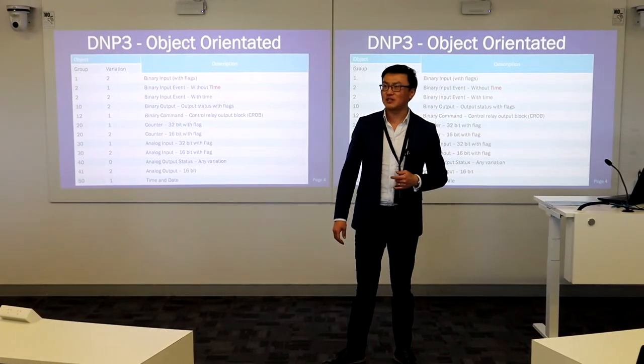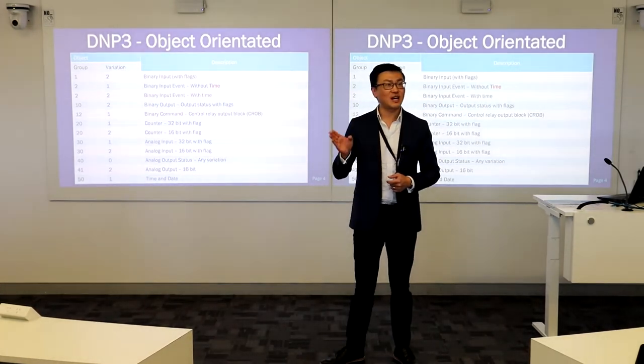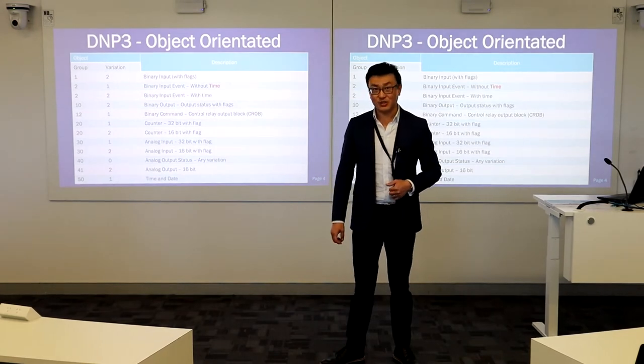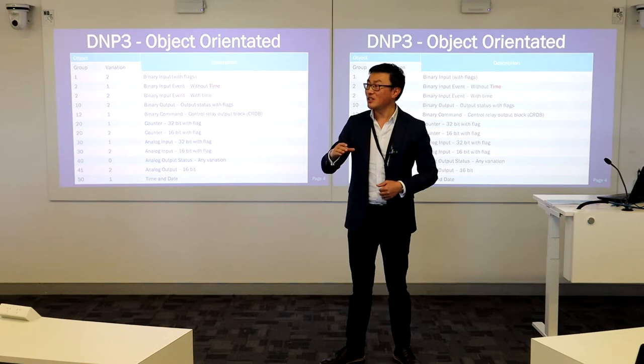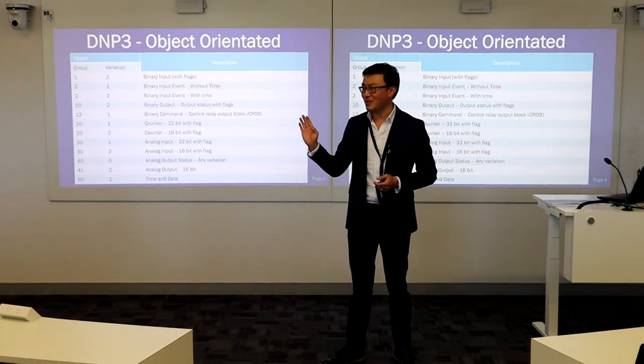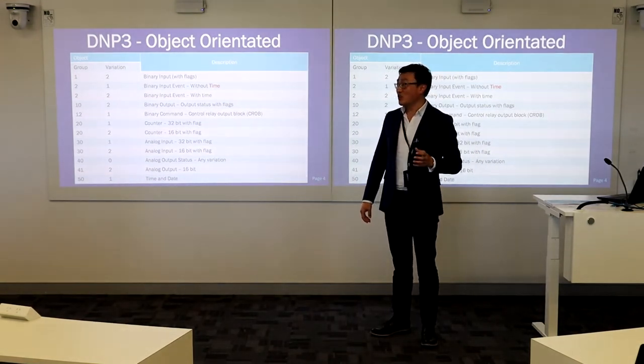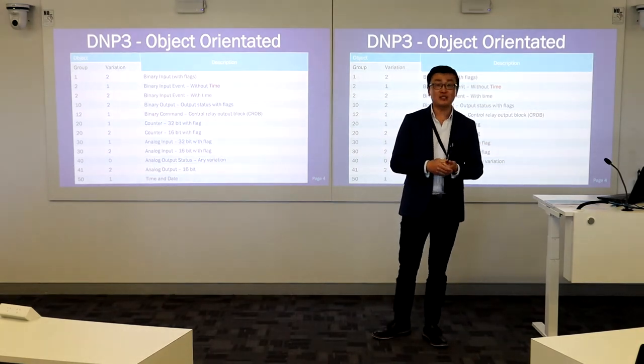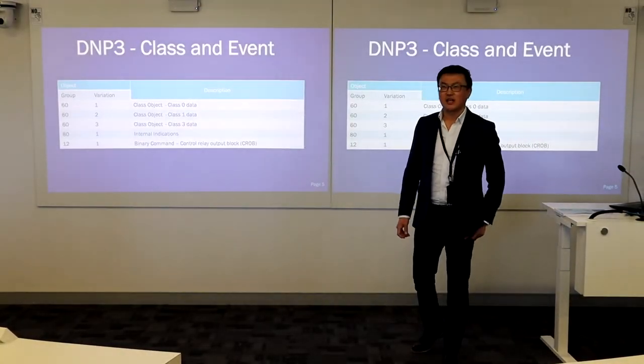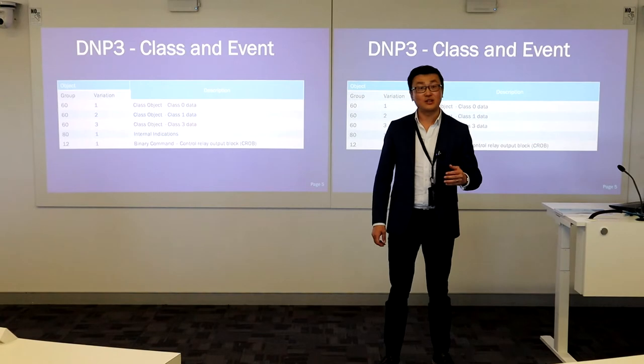The RTUs or DNP3 outstations usually have a feature to request time from the master as well, just in case. There is a specific setting in the E-Series configurator to periodically do that — for example, every half hour or every 24 hours request the time, and the master will then send a time record down. Industrial communication is all about management of bandwidth, management of records, and management of data integrity.